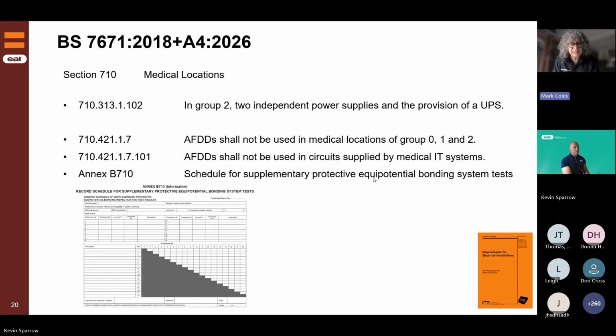The last point is the schedule for supplementary protective bonding system tests. If you've been in a hospital recently, you might see in certain areas the bonding busbars, possibly behind a glass panel, all labelled up with the nuts tightened on them, green and yellow. These are supplementary bonding connectors bringing everything back to a central point, maintaining equal potential across anything metal, bolted together. Going back to my first point about open heart surgery, the last thing you want is for potentials to appear across equipment.